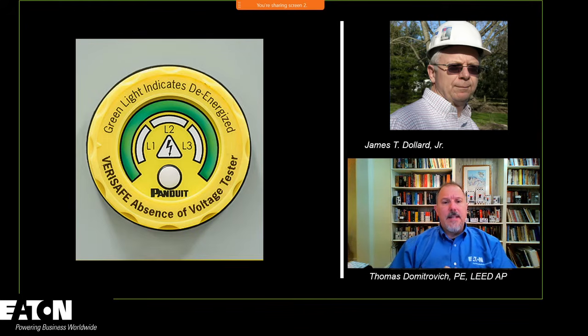of voltage tester that's out there, and when you take products like these and combine them, it's like layers of the onion, where you can turn something off and you still have to verify that you've done that, and you have to do that process of establishing an electrically safe work condition. Things like this, and things like the arc reduction maintenance switches, things like taking the main out of that panel board, putting it in a separate enclosure so that you can de-energize and establish that electrically safe working condition, where you open that enclosure and there's absolutely nothing energized inside. Those are all steps that can only be taken before you get out there and you're actually installing anything. So that's got to be a part of the design phase, in my opinion.